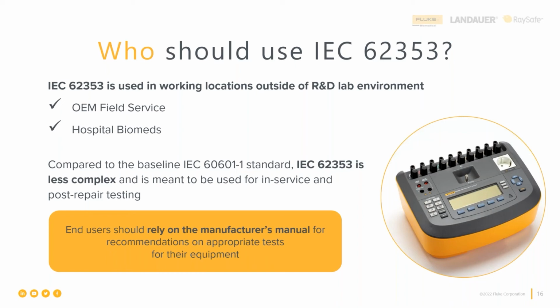particular medical device. But the 62353 is intended for us to use ongoing, every year, after every repair, on incoming inspections, all of those situations where a medical device may be tested over and over and over, and measurements will be made for electrical safety. So that's the difference. And 62353 is therefore our friend and a very appropriate standard to use even under NFPA 99 because it more than satisfies the requirements for measurements in NFPA 99.